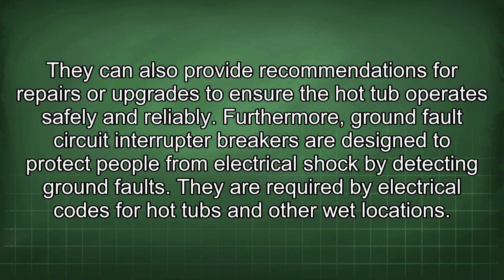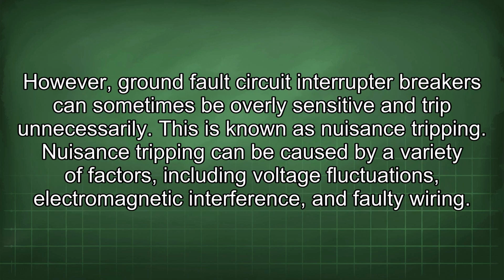Furthermore, ground fault circuit interrupter breakers are designed to protect people from electrical shock by detecting ground faults. They are required by electrical codes for hot tubs and other wet locations. However, ground fault circuit interrupter breakers can sometimes be overly sensitive and trip unnecessarily. This is known as nuisance tripping. Nuisance tripping can be caused by a variety of factors, including voltage fluctuations, electromagnetic interference, and faulty wiring.